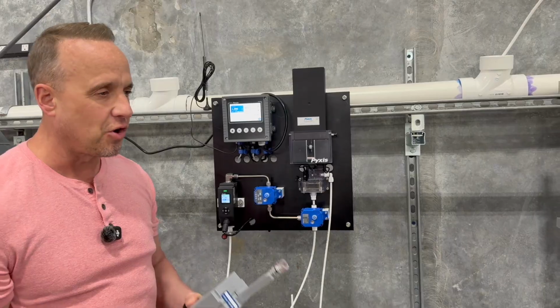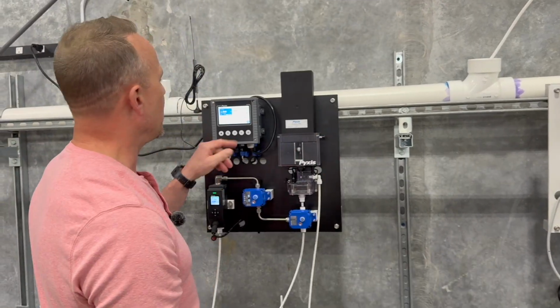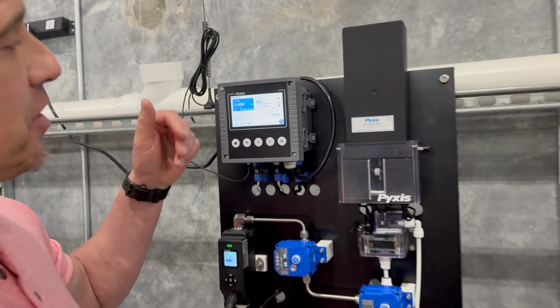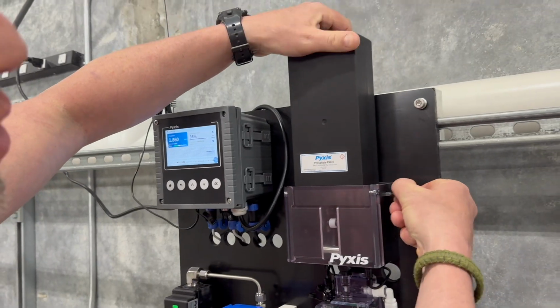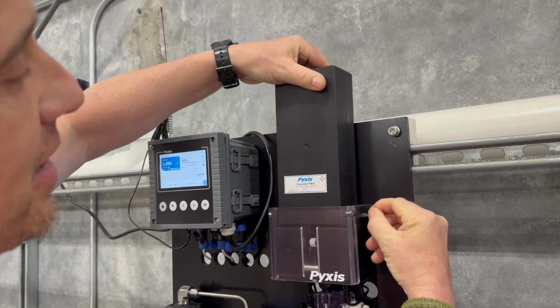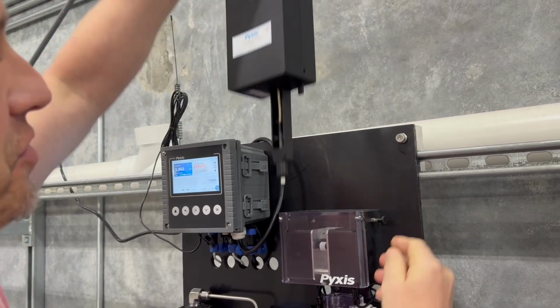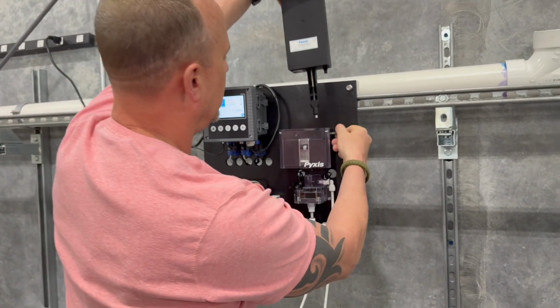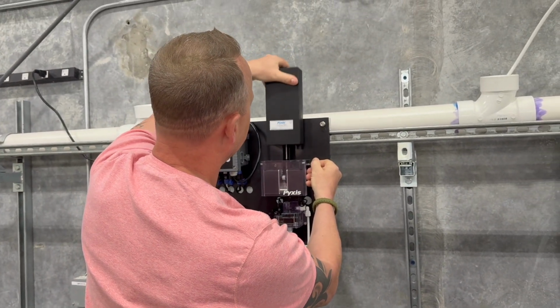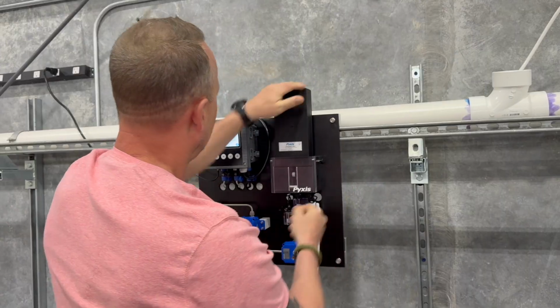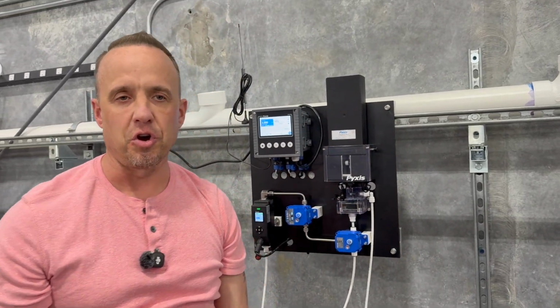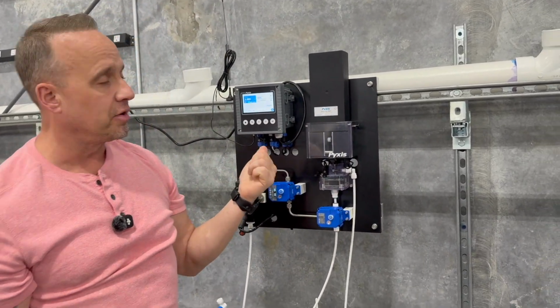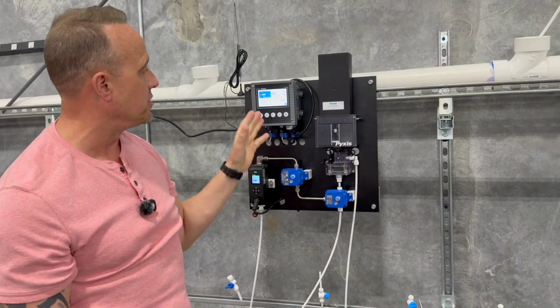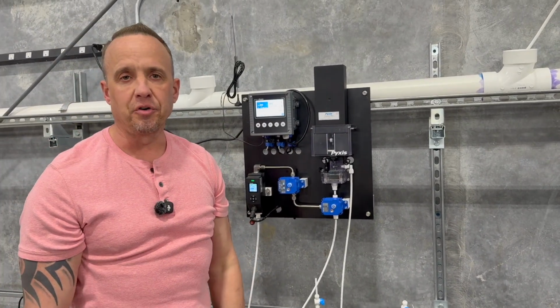The replacement of these cartridges is super simple. You'll go into here and tell the unit that you're actually going to be replacing the cartridge. You'll unlock the cartridge mechanism and remove the cartridge. And when the new cartridge comes, unlock the mechanism, slap it in place, and tell the unit that you've put in a new cartridge. Very essential that you do tell the unit that you've installed a new cartridge so that you can get inventory readout during the test cycles.